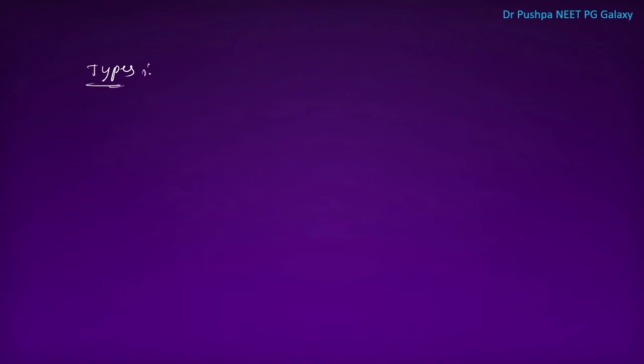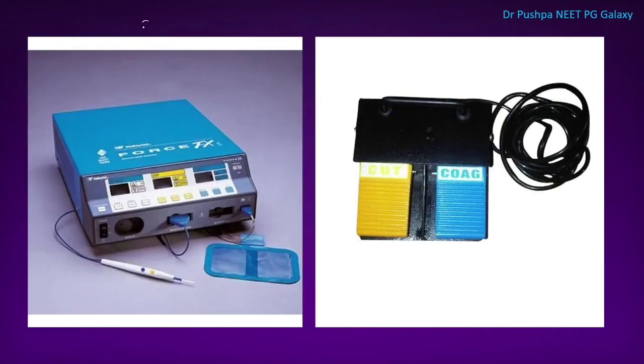There are two types of cautery: monopolar and bipolar. On the cautery machine, the foot pedal is used to control the cautery. The yellow color setting is for cutting and the blue color is for coagulation.